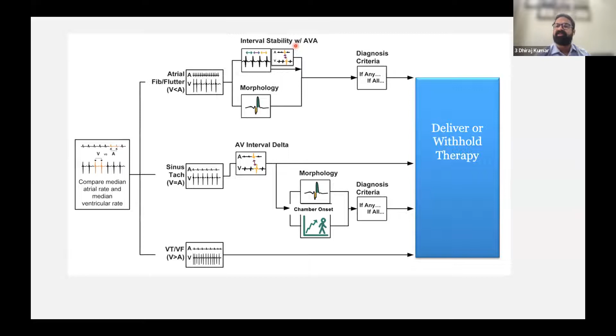For single chamber ICDs, it looks at only three things, so there are three suppositions. VTs have abrupt onset, SVTs may or may not have abrupt onset, but sinus tachycardia has a gradual onset. So if there is a sudden onset, it thinks of it as a VT. But if there's a gradual onset, the device knows that this is sinus tachycardia, so it does not provide any therapy. Morphology changes in VT, so the device can understand the morphology by comparing to the sinus template that it has stored. And finally, it is important to understand whether VTs have stable intervals. Just at the onset, there might be a bit of variation, and towards the end, there might be a bit of variation. But VTs have stability, meaning the cycle length of VT is fixed and varies within 40 milliseconds. That is the other criterion that it looks at.